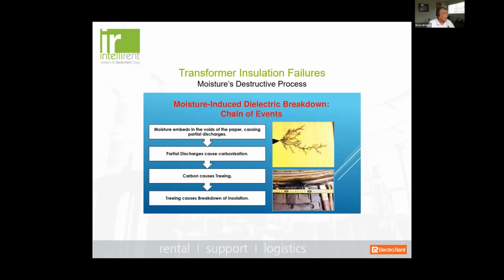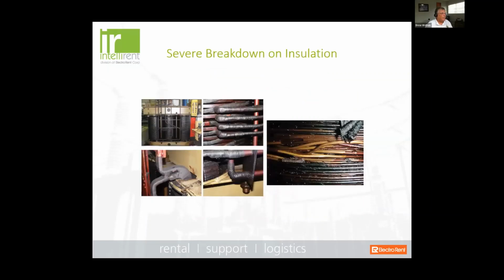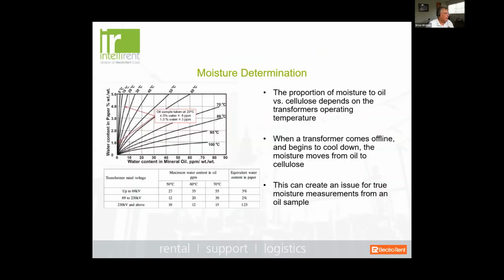So it's kind of a chain effect. The moisture embeds in the voids of the paper, causing the discharges. That leads to carbonization, and that can lead to a treeing condition, and that can cause a severe breakdown in the insulation, as we see in this illustration right here. And here's just a look at how some of that can appear, and it doesn't damage just the windings. You'll see here other components of the transformer where the insulation is severely broken down because of moisture.